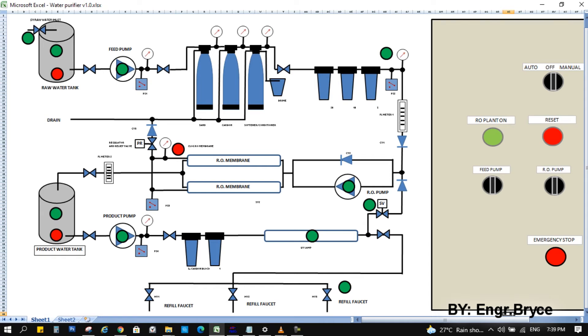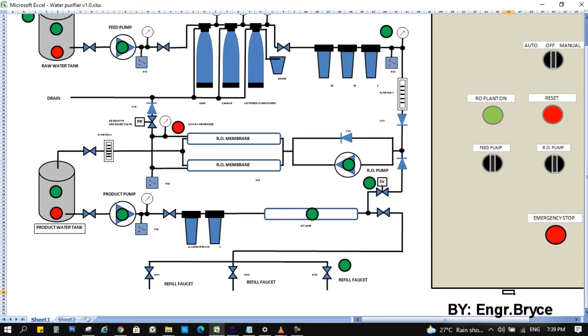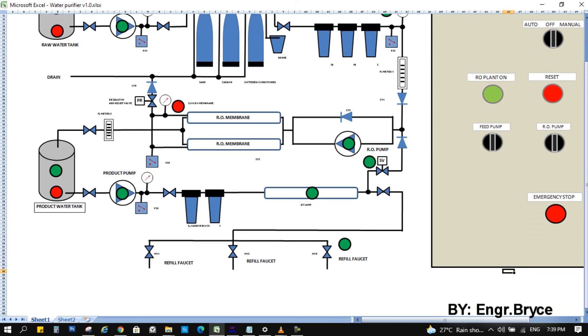The RO pump start only if feed pump is running, pressure in the suction line, and no existing alarm. And the pump stop if tank 2 is full, and over pressure in the suction side, and over pressure in the discharge line will also trip the pump.